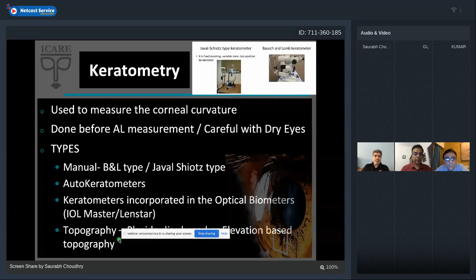Now, where are the errors coming from? It is the improper calibration of your instrument, the faulty positioning of the patient, improper fixation of the patient, an accommodative fluctuation by the examiner, a localized corneal epitheliopathy or a defect, excessive tearing, abnormal lid position, and improper focusing of the corneal image. You do need to look at all that.